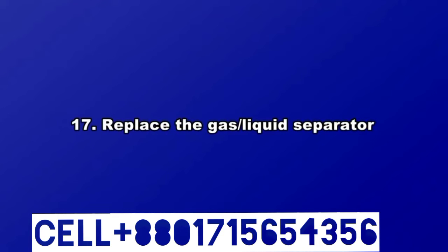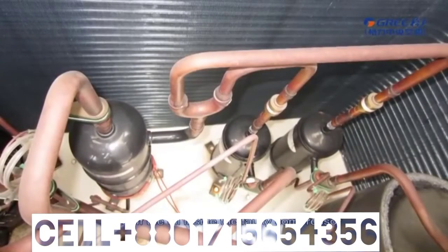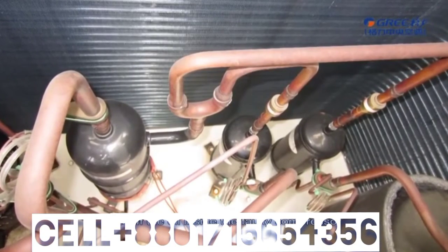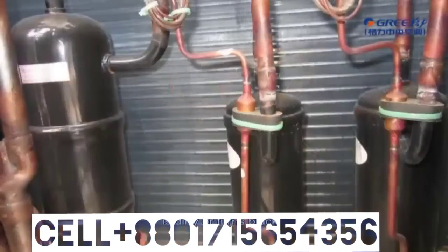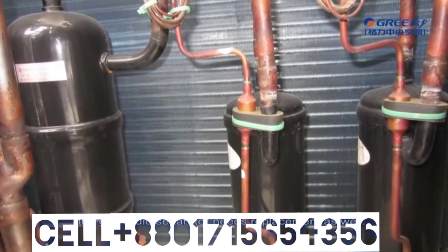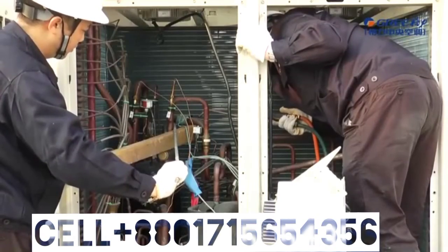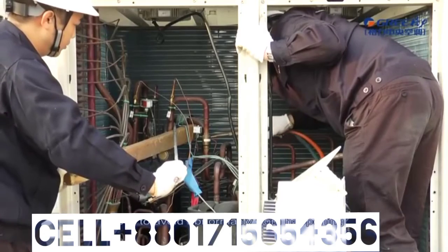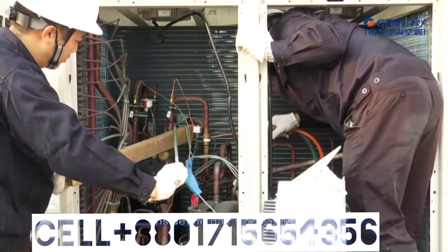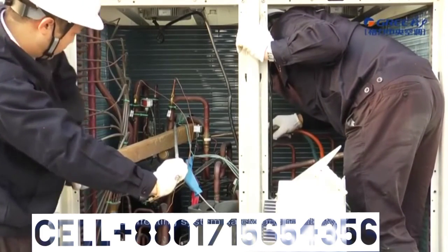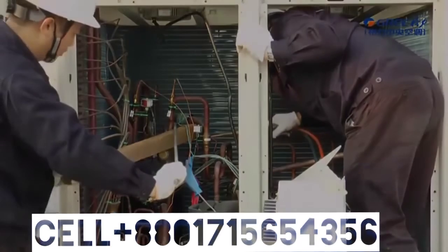17. Replace the gas-liquid separator. Note: if the oil inside the faulty compressor is dirty or turns black, the gas-liquid separator needs replacement as well. This is to avoid abnormality from happening inside the gas separator and affecting system safety and reliability.